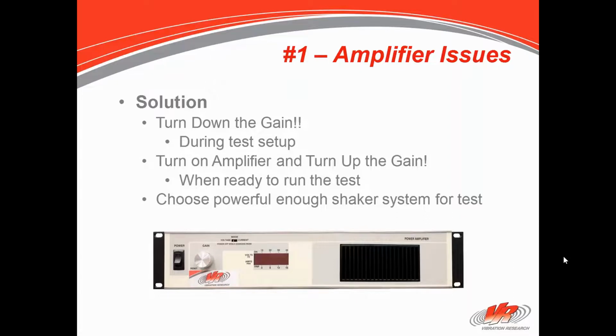So that is the only reason why you would keep the gain at less than 100%. Well, I guess safety reasons too, it would limit the shaker output to some extent. So again, use the gain as needed, but it's not going to wear out your amplifier or anything like that.